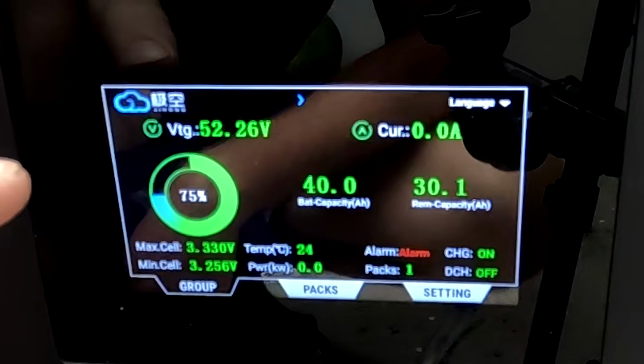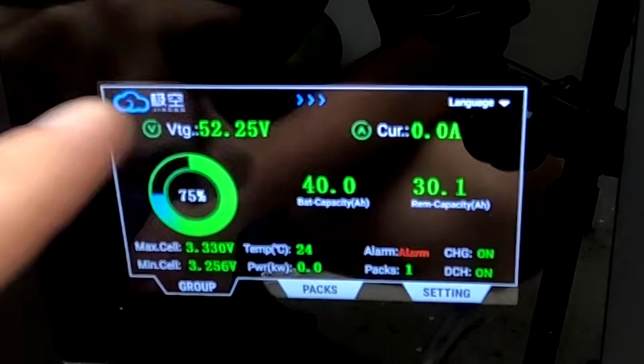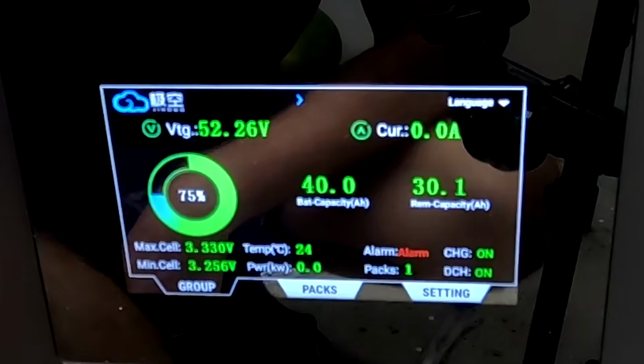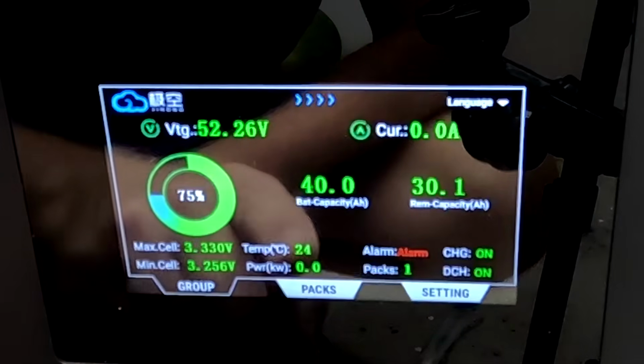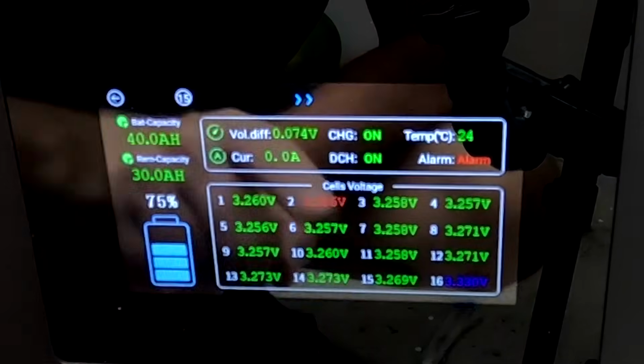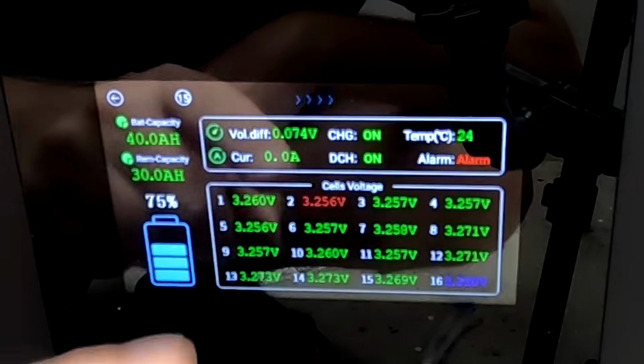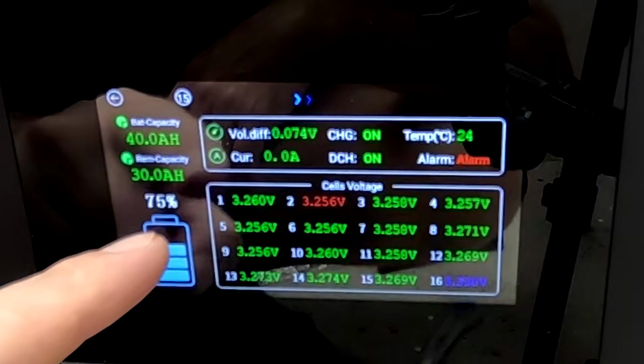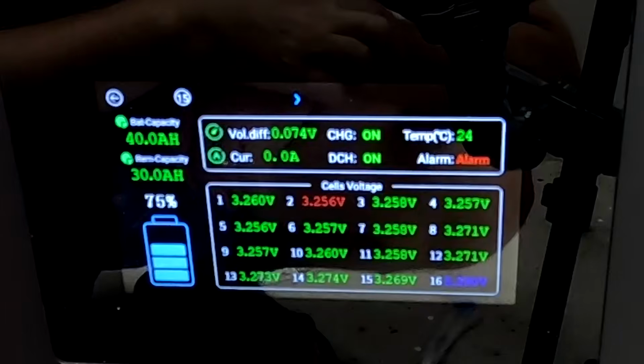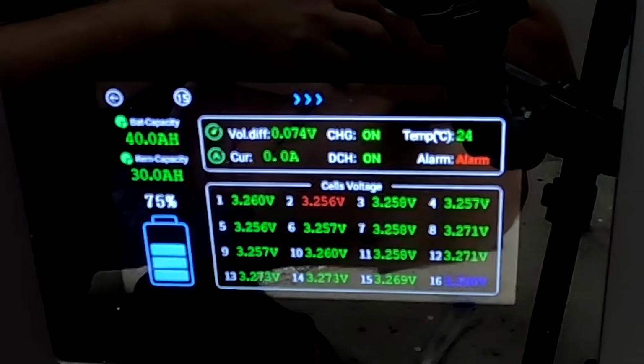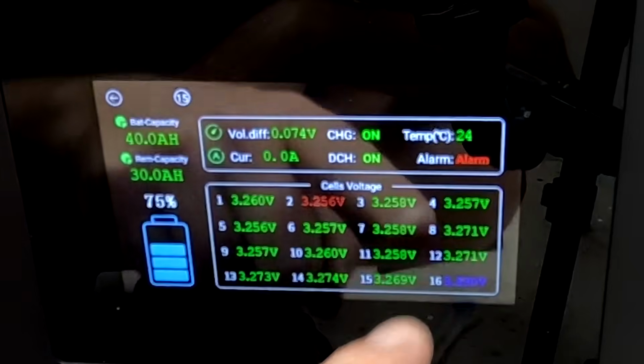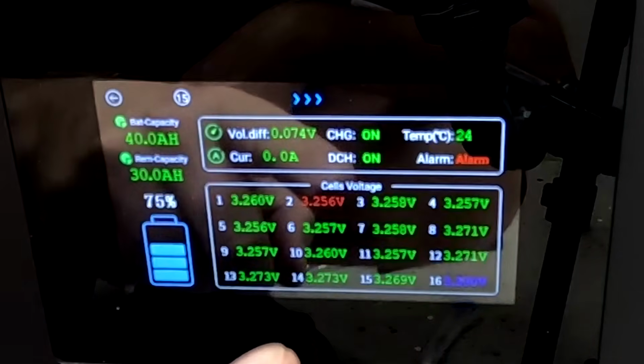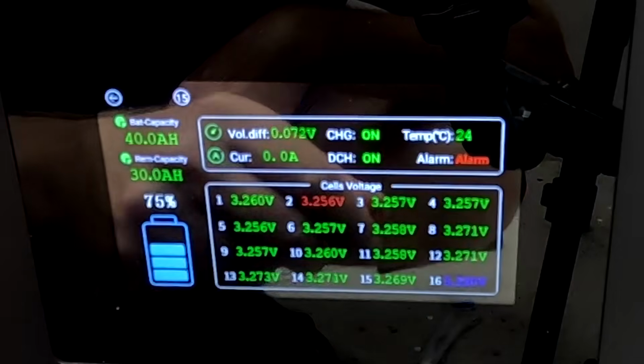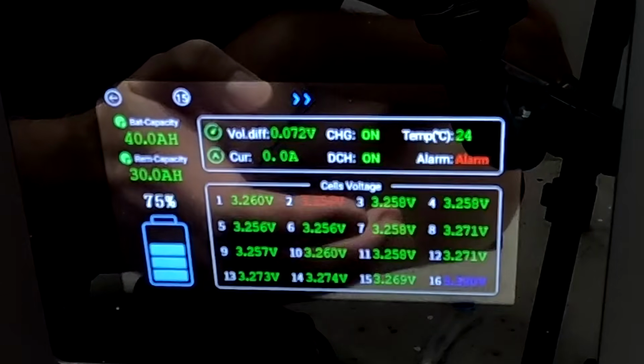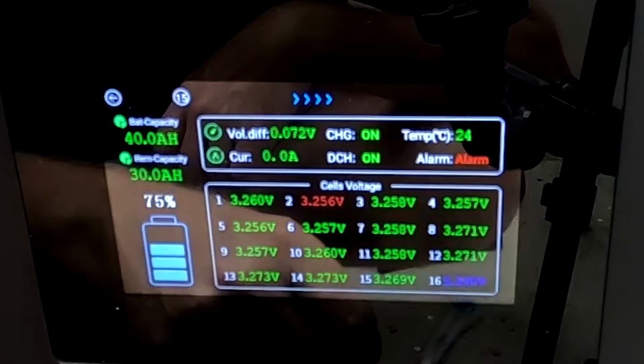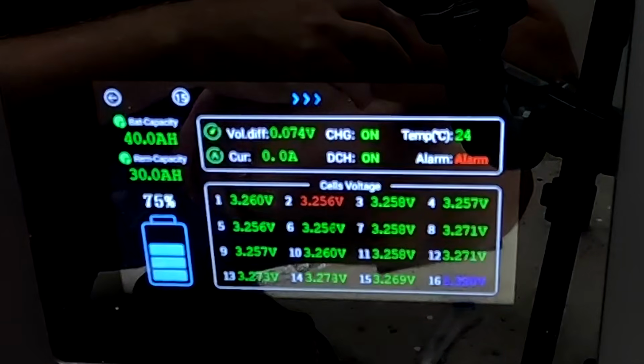That is good. I've got an alarm, which we cannot see because this display is not on the newest version, but the BMS hasn't been set up for this battery yet. Let's just have a look at the packs. There's one pack, let's check on all the cell voltages. 3.26, yeah, cell number 2 is the lowest, 3.256, and cell number 16 is the highest, which is our MB56 cell. That's alright, no problem. It will be always the highest cell probably because it has 140 ampere hours more than all the other cells. That is just the nature of the beast now. Okay, that all looks pretty good.